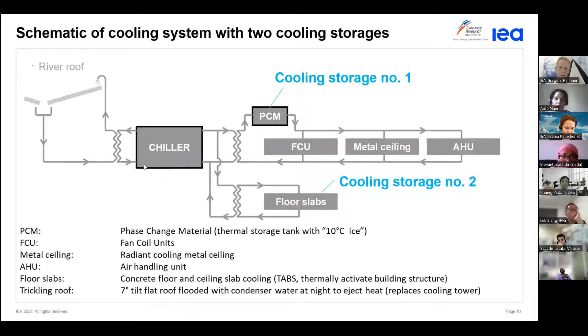Another innovation is that at night, because the building was designed for this chiller to only run at night, instead of installing a cooling tower, we actually designed it with a so-called river roof. So we had this manifold pipe on top of the PV roof and just let the water run across the solar cells, as you can see here.